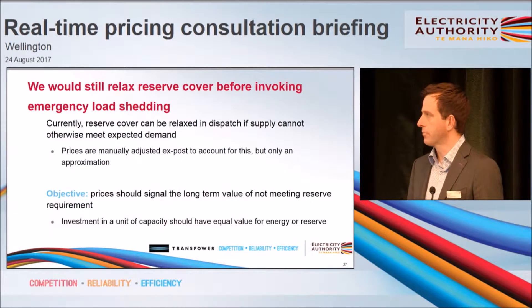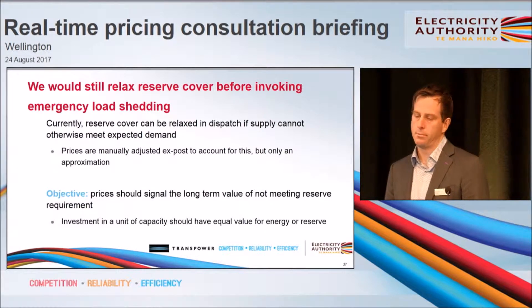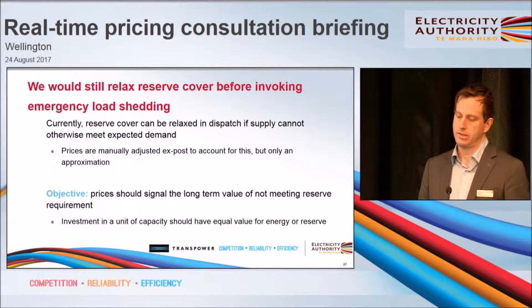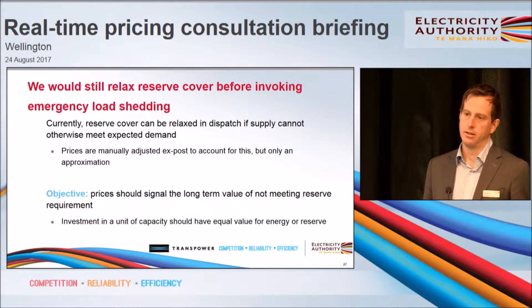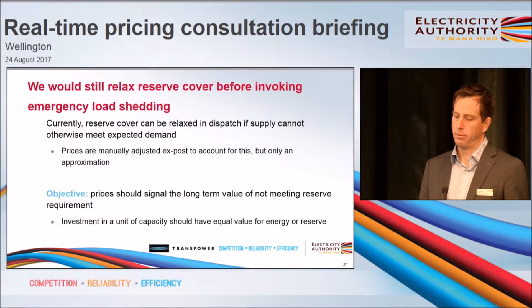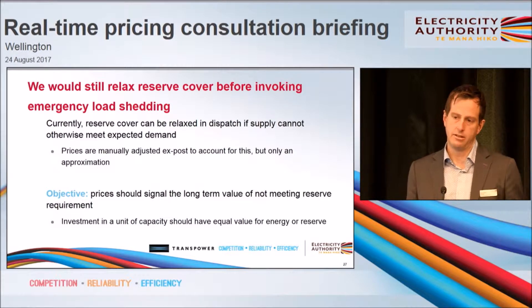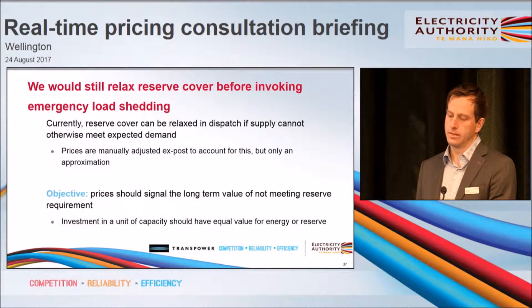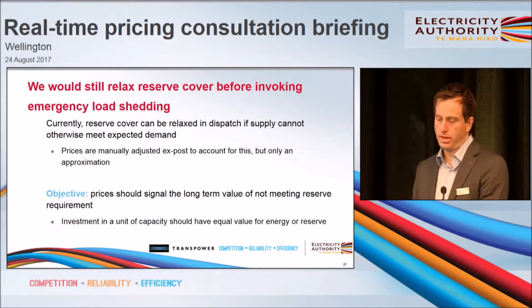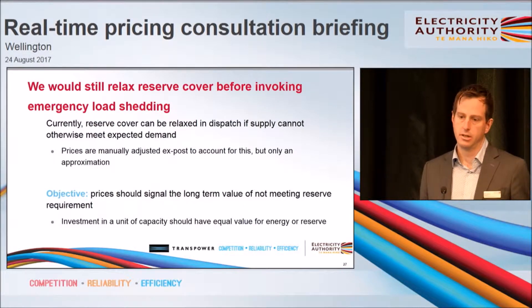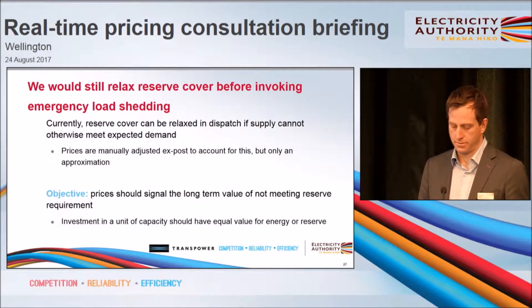So today, reserve cover could be relaxed in the dispatch schedule if supply could not otherwise meet expected demand. Meaning that you take the pragmatic decision that it's better to temporarily have reduced security by sacrificing some of that energy being currently held back for reserve, and instead use it as energy to supply demand in real time, because if you don't, then ultimately you're going to end up in some sort of load shedding circumstance.